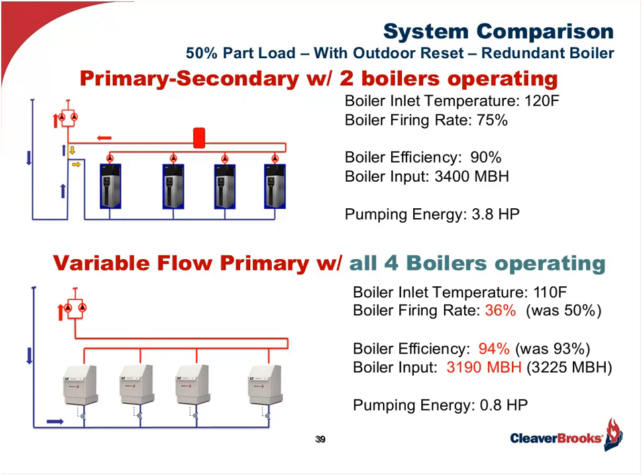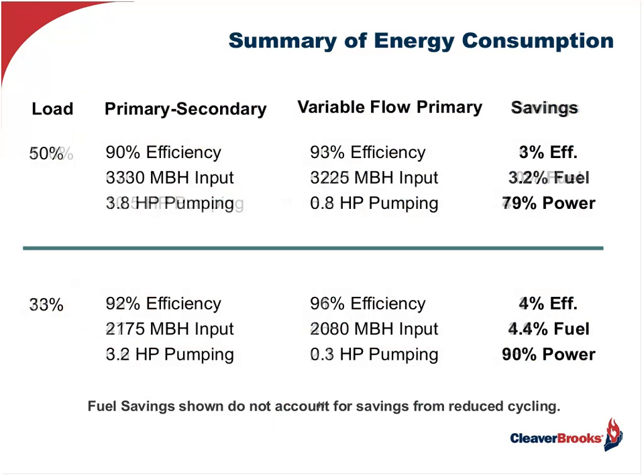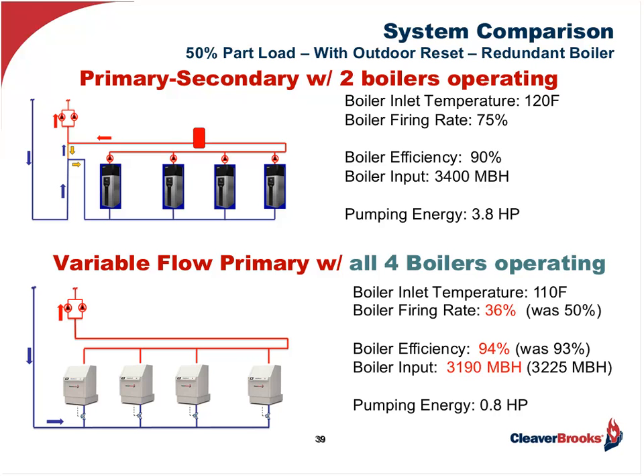If you have extra boilers with variable flow primary at certain conditions, you can make use of that boiler because now we could run water through all 4. Again, high mass boilers have no minimum flow. So we can take that GPM down by running water through all 4 of them. Our firing rate goes from 50% to 36%, and we pick up a percentage in efficiency. So that capital cost that you have sitting there is now actually making you a little bit, or saving you a little bit of money.